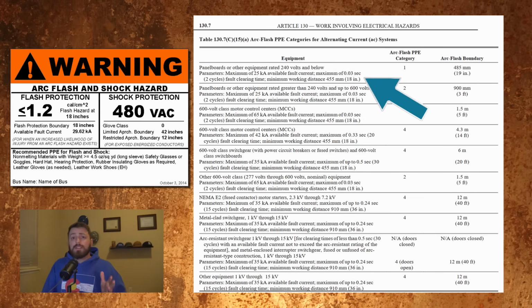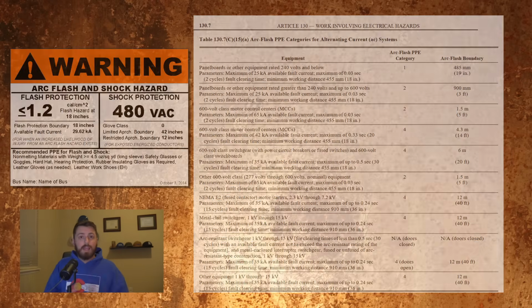It should be evident that the further away from the source of an arc flash you are, the less energy you'll receive. They can put a different incident energy rating on the sticker depending on the distance you're going to be from the bus doing the task. That's something you want to keep in mind if you're just a dude with short arms.